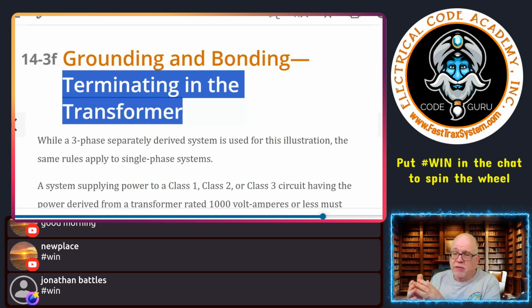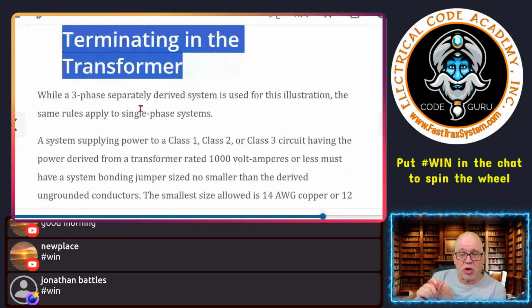Most of the time you're supplying a panel to have additional loads. So in there, separate neutrals and grounds, everything, just like you would for a remote distribution panel in a garage or in a basement or whatnot, running 4 conductors up. You isolate the neutrals and you connect the equipment grounds to the case, right? Separation, very common. We all follow that rule. But that's when I put the system bonding jumper actually in the transformer, okay? Now, while the illustration that we're gonna look at is showing a 3-phase separately derived system, it's just an illustration. Don't think that this is not the same rules that would apply to a single phase system. Exactly the same rules, okay? When it comes to the grounding and bonding, exactly the same type of methods and rules, right? Just think, electrons don't care. So you follow all the same rules, so don't make it overly complicated, okay?